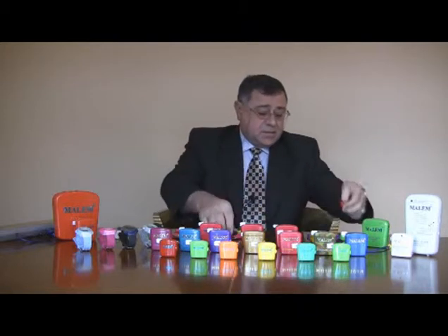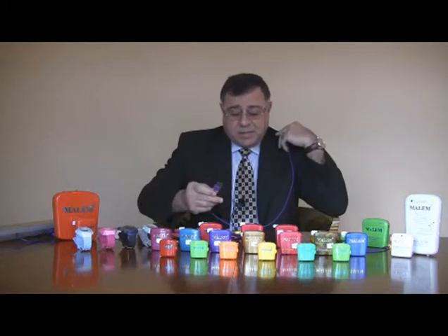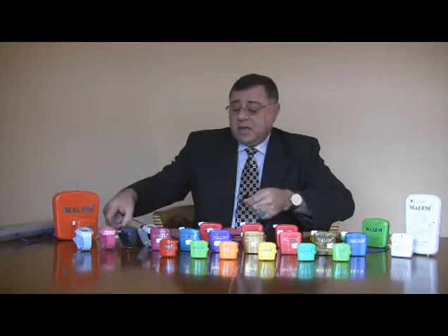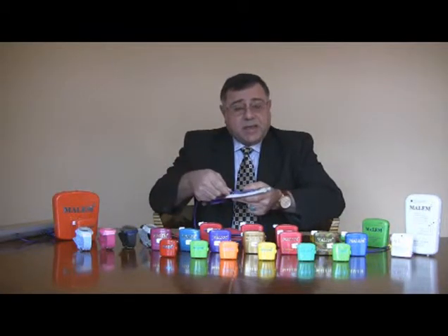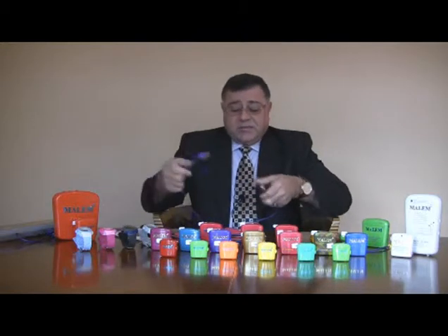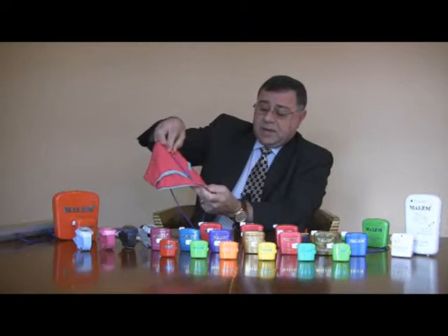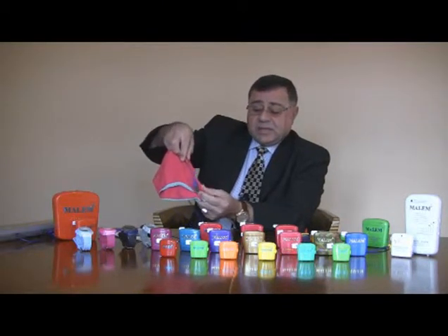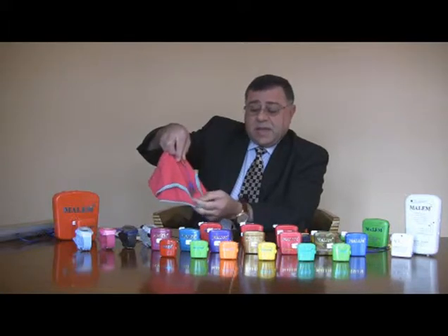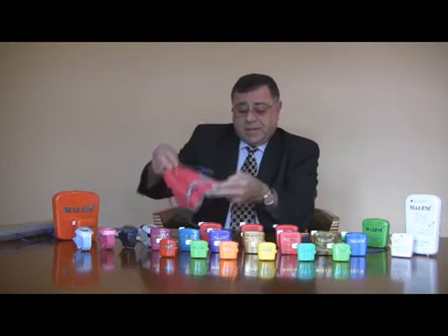If you are using the standard sensor, again, plug it in, attach the alarm as described, and you have two ways of using this sensor if you wish. You could either use any sanitary towel, cut in half, insert the sensor between the layers, use the crocodile clip to anchor it in position, and then stick the pad inside the pants. Alternatively, you could attach the sensor on the outside of any underpants, use the crocodile clip to anchor it, and then wear another pair of underpants so that the sensor is located correctly and in contact with the material, so the alarm will go off as soon as the material gets wet and the sensor is not flying away from the material. So it's important to sandwich it, either between two pairs of underpants or use a pad.